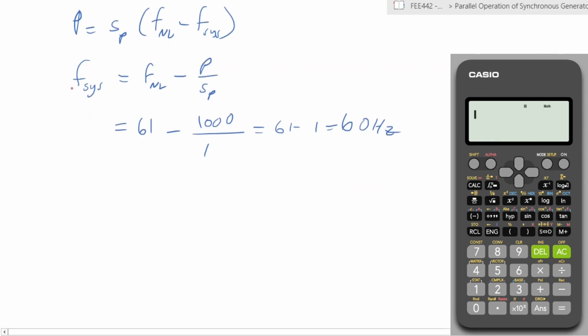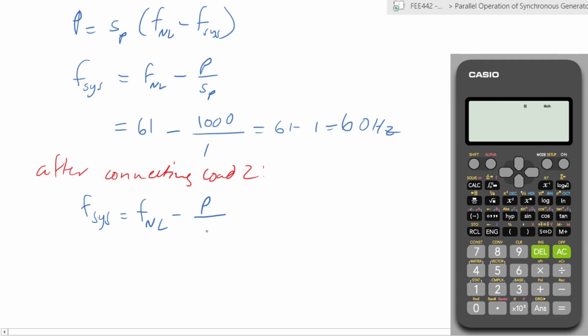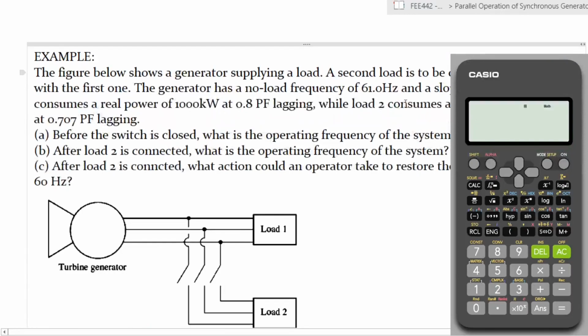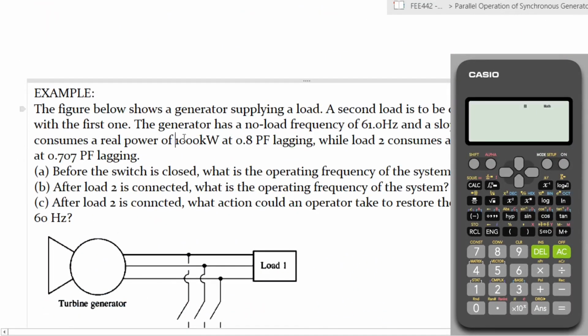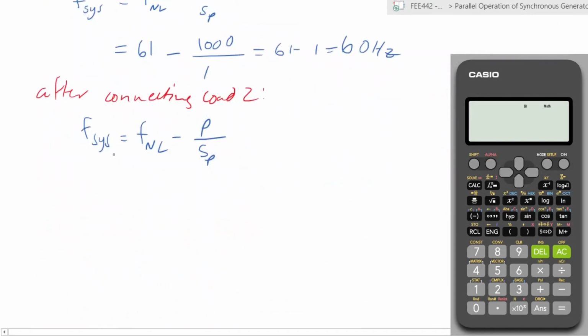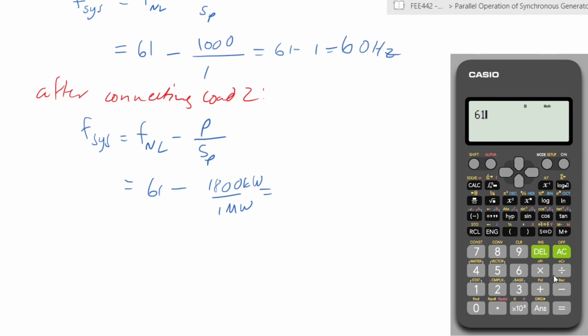After load 2 is connected, the system frequency is equal to the same thing. We've not changed the set points, but the power has changed. Instead of 1000, we have 1000 plus 800. So it is this 1000, and then you have the real power of 800. So the two of them would be 61 minus 1800, so 1000 plus 800, over 1 megawatt. The reason for the change is this is in kilowatts and this is in megawatts, right? So you can subtract them. So 61 minus 1.8 gives us 59.2 hertz. Okay, that's after connecting load 2.